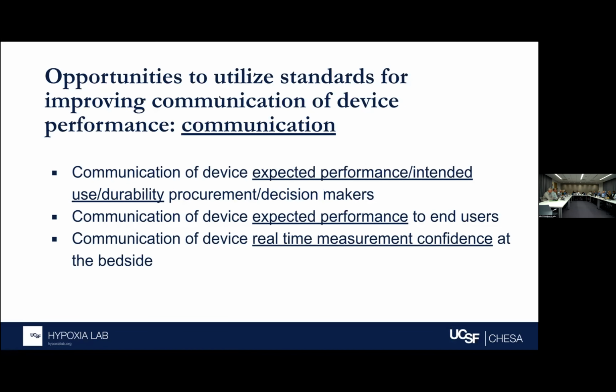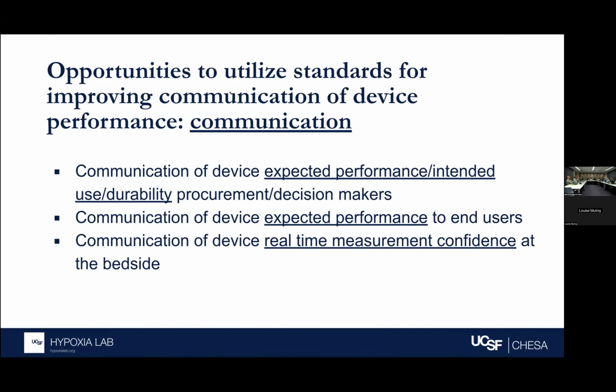I just thought it was worth raising that in the UK, there are 4 classes of risk for devices: 1, 2A, 2B, and 3. Within that, devices for continuous surveillance of vital physiological processes, anesthesia, intensive care, or emergency care are considered class 2B, whilst those intended to be used to obtain readings of vital or physiological signals in routine checkups and self-monitoring are 2A. But these would both require the oversight of a conformity assessment body as part of the conformity to the regulations. It wouldn't be the MHRA looking at that, it would be the approved bodies, conformity assessment bodies. I didn't know if that was useful or interesting.